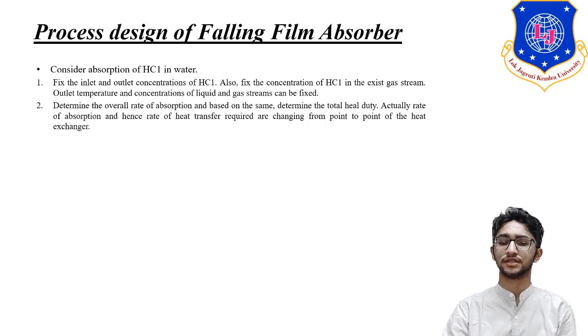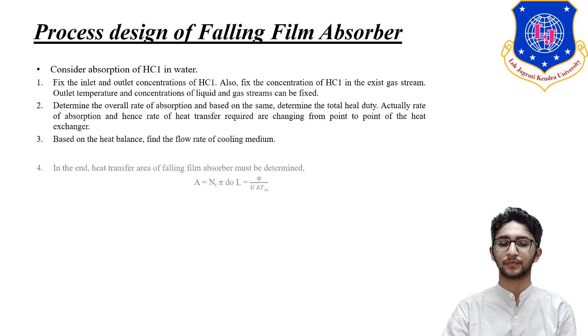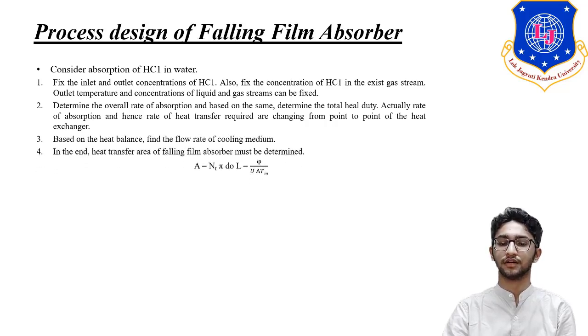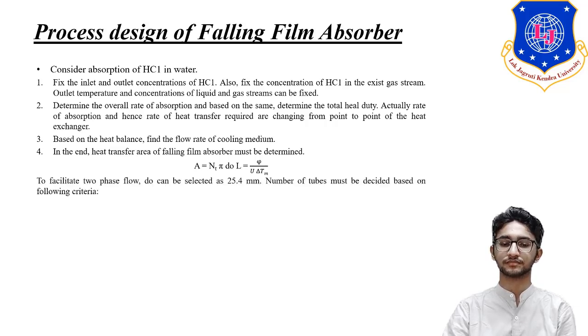The rate of absorption and the rate of heat transfer required are changing from point to point in the heat exchanger. So based on a heat balance, we will find the flow rate of the cooling medium, and in the end the heat transfer area of the falling film absorber must be determined. So the equation for the same is A equals Nt into pi d0 L, which equals Q upon U delta Tm.